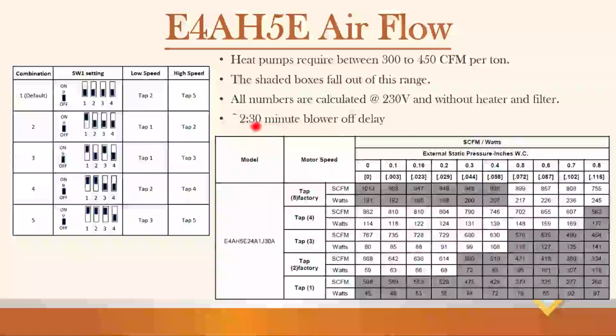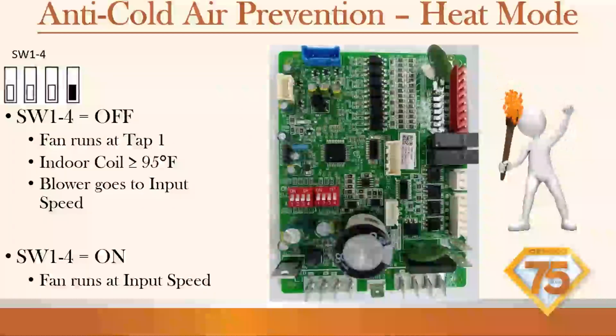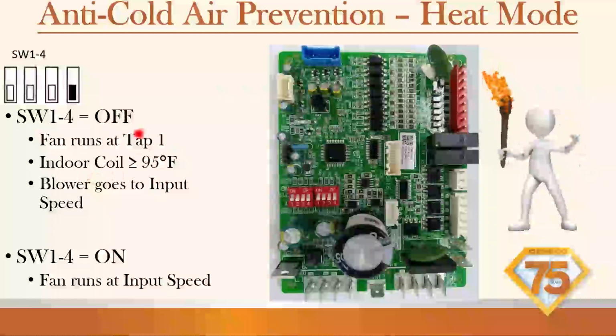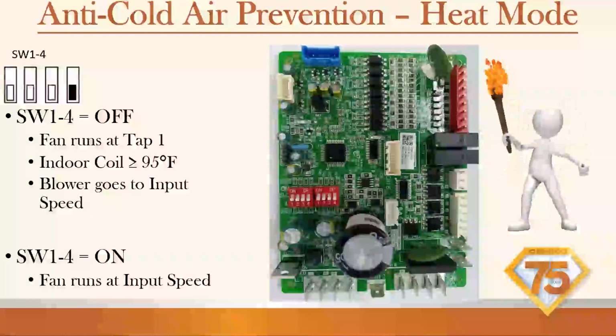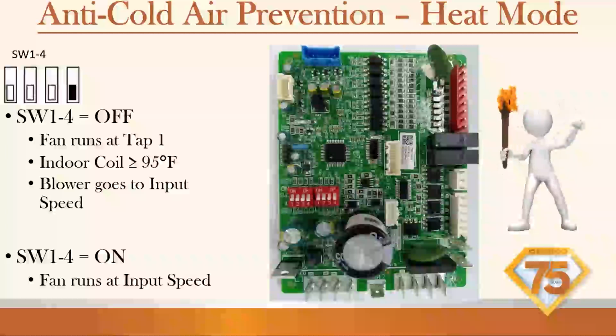There's a 2.5 minute blower off delay. So it'll run for an extended 2.5 minutes after a call for heating or cooling has been satisfied. So for these dip switches, we do have a cheat sheet on what recommended settings Gensco goes off of. You can ask your sales rep or text into tech services with the email address, and we can send you the recommended dip switch settings. So you can print off and have on your install rigs. Take out some of the guesswork.